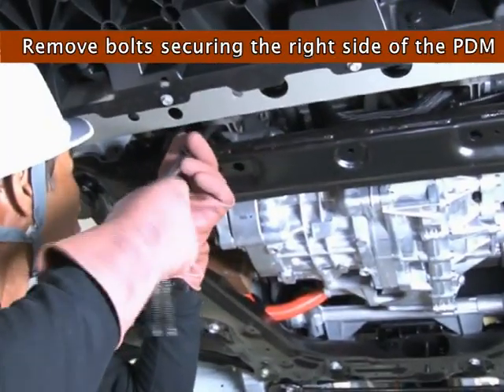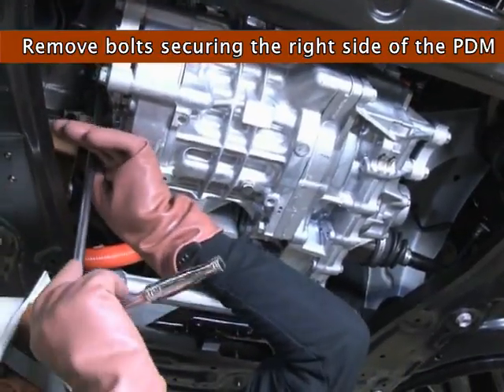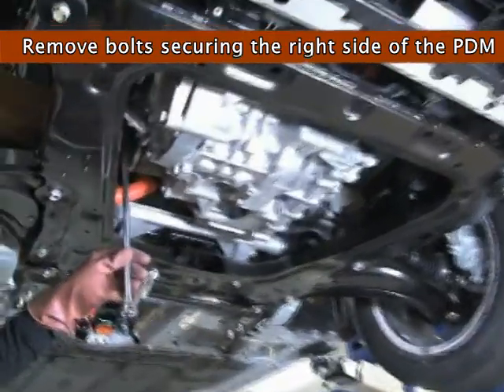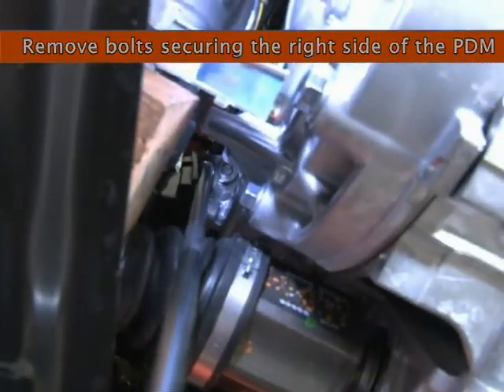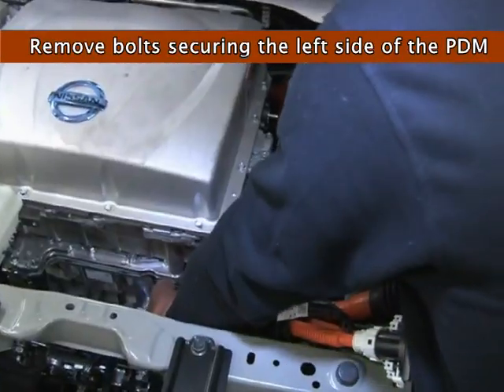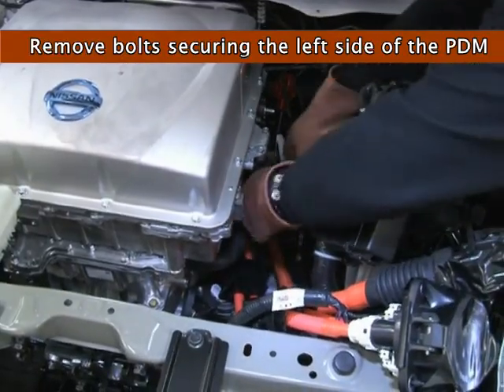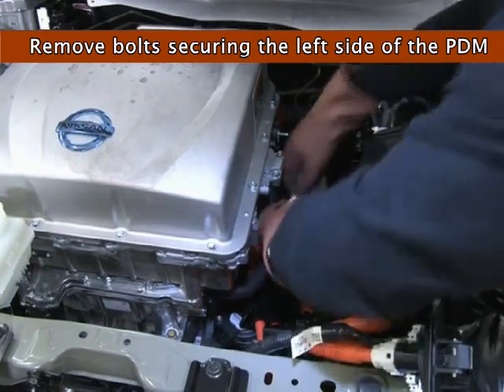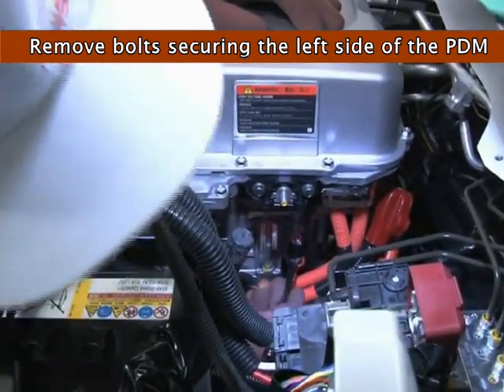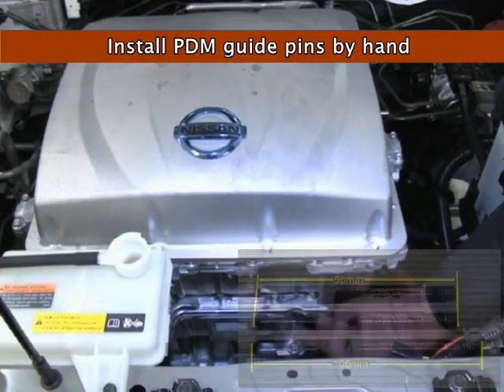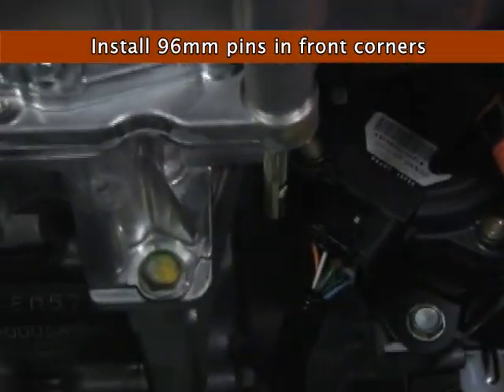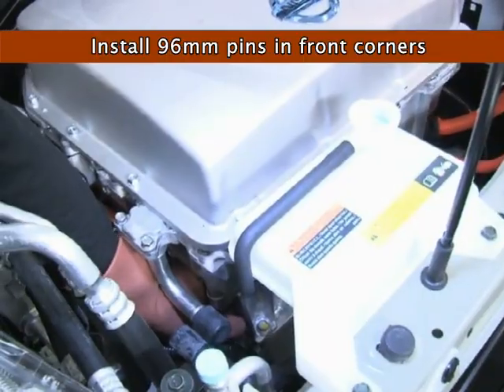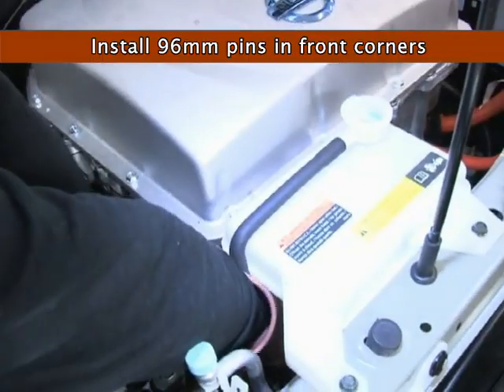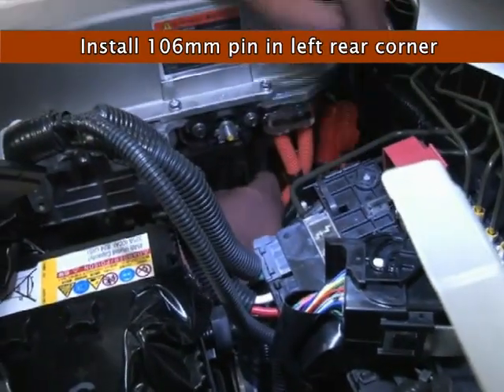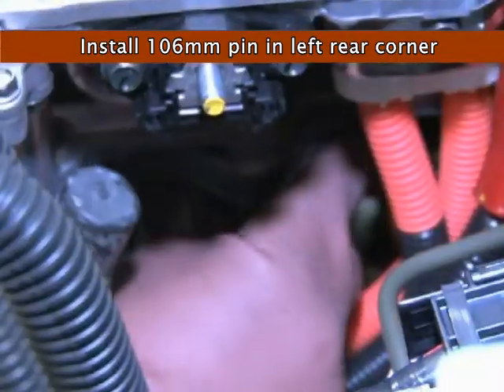Remove the 3 bolts on the right side of the PDM that secure the PDM to the inverter. Remove the 3 bolts on the left side of the PDM that secure it to the inverter. Install the 3 PDM guide pins by hand into the holes for the bolts you just removed. The 2 96mm guide pins should be installed in the left and right front bolt holes. The 106mm guide pin should be installed in the left rear bolt hole.